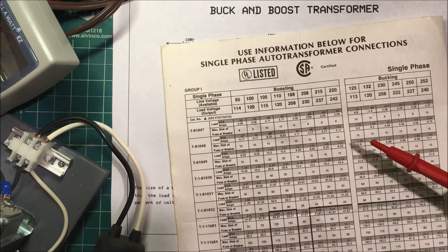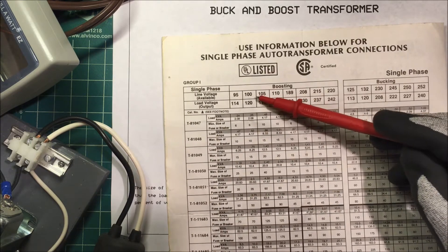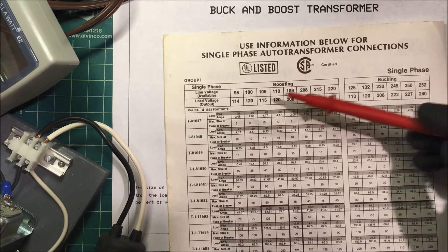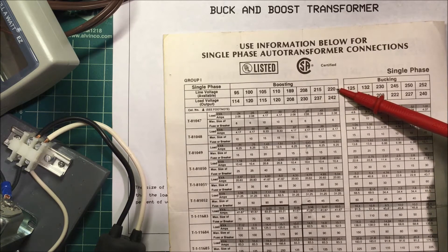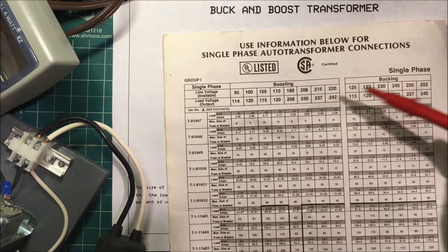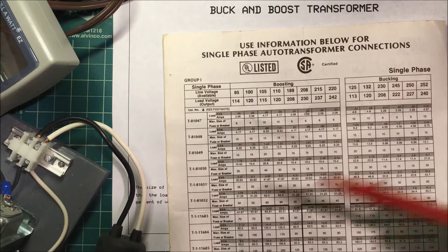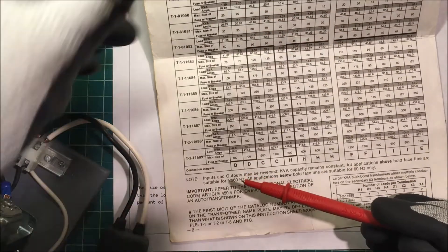Here's a chart from Alvinco — Jefferson and Square D also make these transformers. You can go from 100 to 120 volts, 110 to 120, 208 to 230, or 220 to 240 volts. You can also go the other way, for example from 230 down to 208 volts, by selecting the appropriate configuration at the bottom of the chart.